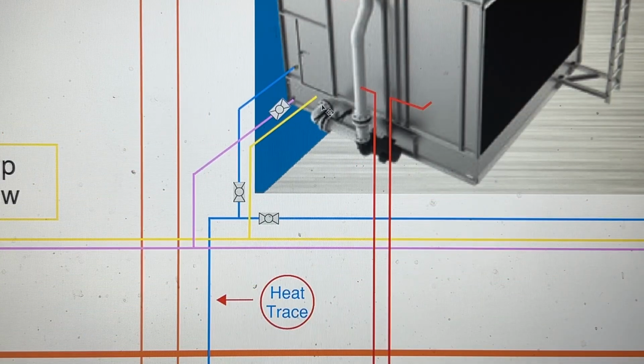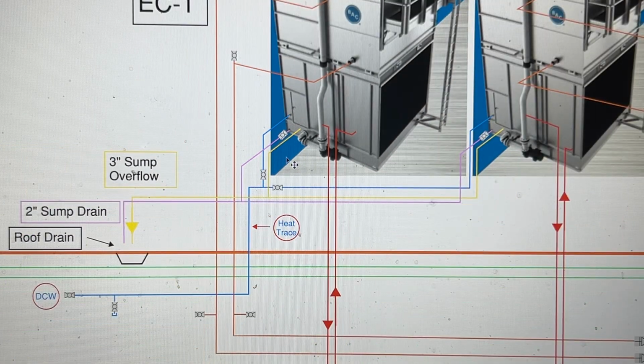The yellow line here is if there were to have a situation happen where the makeup water for the sump were to continually get dumped in there by mistake in some way. Maybe the control valve was stuck or something like that. This would be an overflow line. So if that water rises too far, it will just relieve itself to that same roof drain through this line. This project did have us heat trace the heat pump loop water, because even when this unit is winterized, facilities elects to run the heat pump water through that coil anyhow. So that did get heat traced.